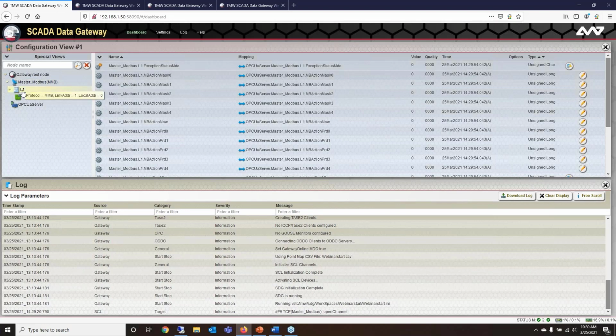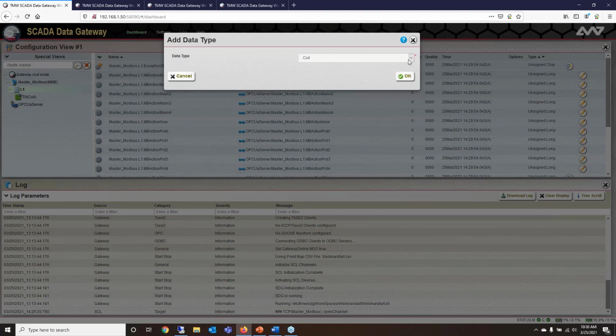We've got this L1, and then we've got the T0, which is the coil data type. If we want to add more data types into this Master Modbus, you go to L1, right click, and select add data type. From here you get this window again, where you can select the other data type you want to add. I'll do an input register and hit OK.